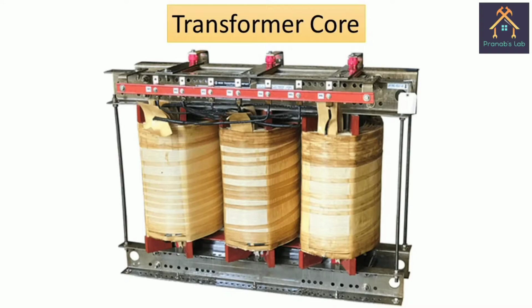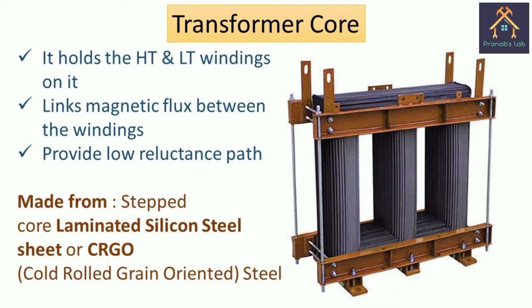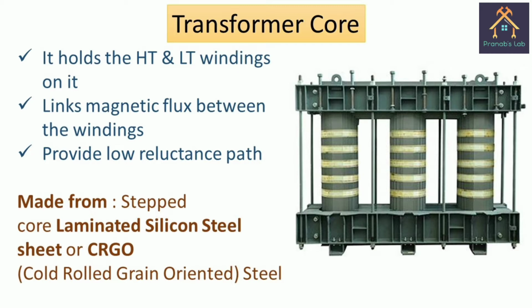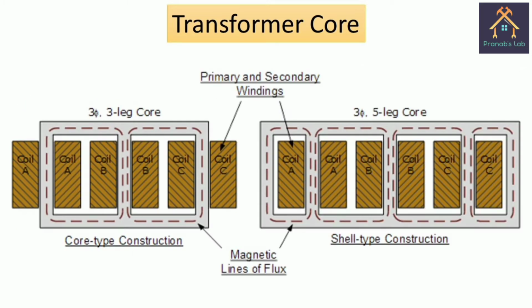transformer. The hidden but vital part of the transformer is the transformer core, which is inserted inside the transformer main tank. The main function of it is to hold the low tension and high tension windings, to link the magnetic flux and to provide a low reluctance path for magnetic flux. To reduce the eddy current loss, the core is laminated, and to reduce the hysteresis loss, the core is made from CRGO steel or silicon steel. There are two types of core construction, core type and shell type. Mainly, core type construction is widely used.